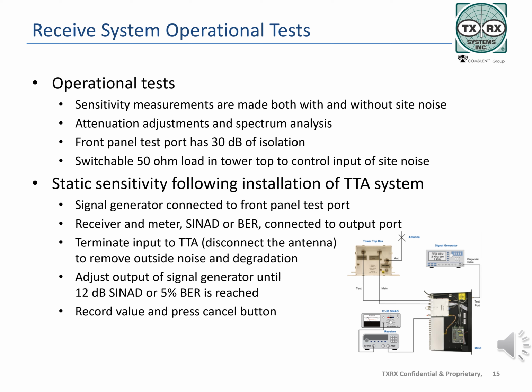During the final operational test, the front panel test port and internal 50 ohm termination will be used. Static sensitivity testing follows a set procedure as fully presented in the operations manual. Once the TTA system is installed, the test for sensitivity changes as the signal generator is connected to the front panel test port instead of at the TTA antenna input. The signal generator should be set up as described in the operations manual to produce a test tone for SINAD testing or the appropriate pattern to test for bit error rate.